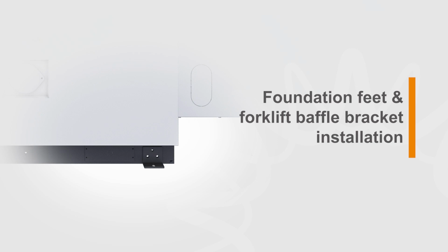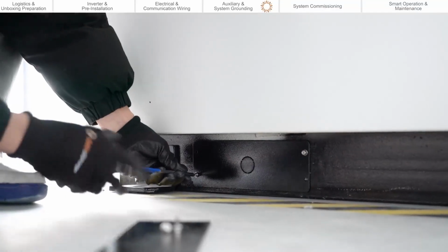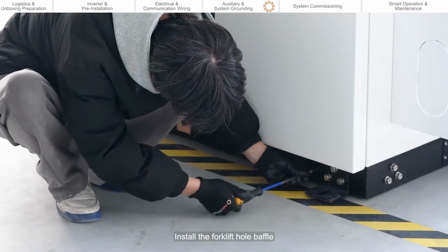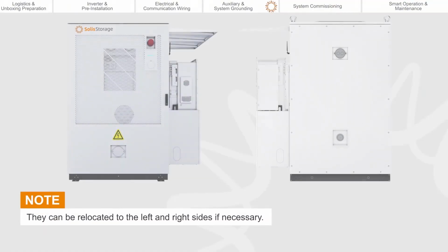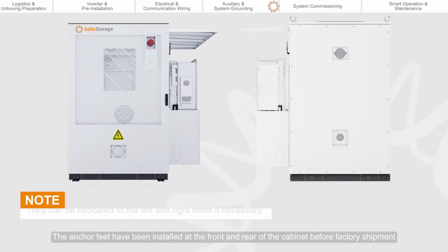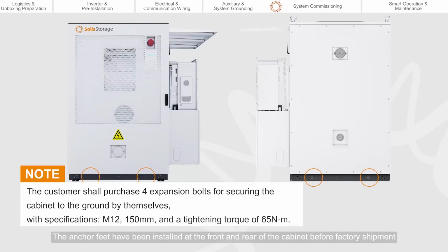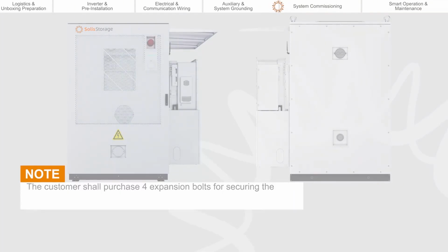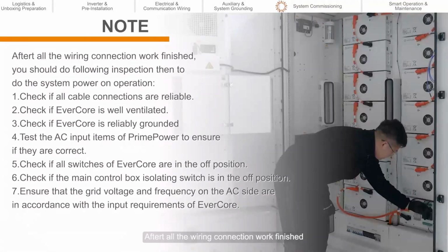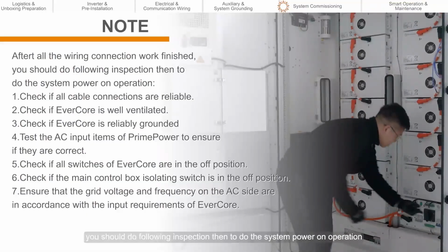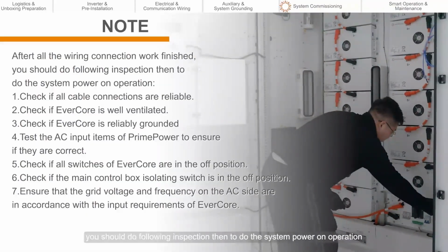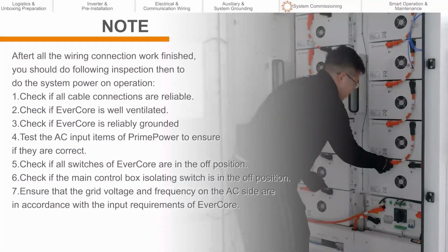Foundation feet and forklift baffle bracket installation. Install the forklift hole baffle. The anchor feet have been installed at the front and rear of the cabinet before factory shipment. System commission. After all the wiring connection work is finished, you should do the following inspection, then do the system power on operation.